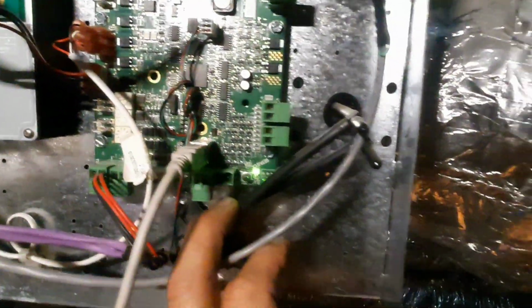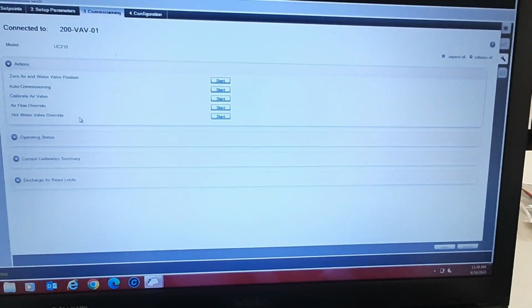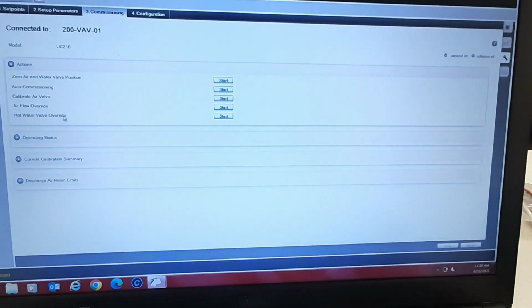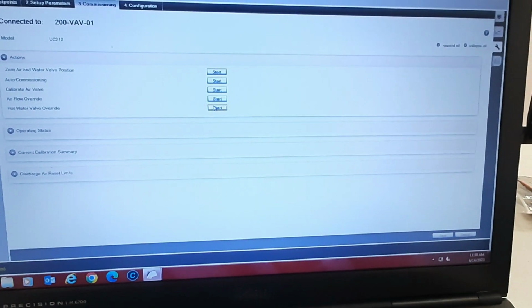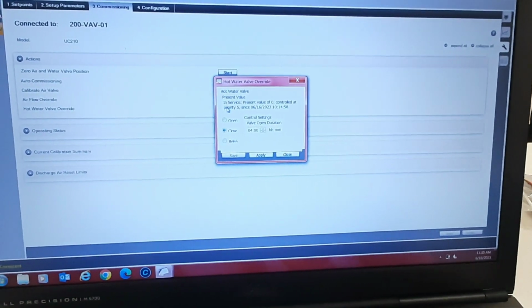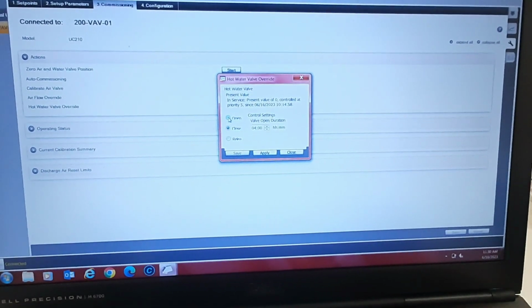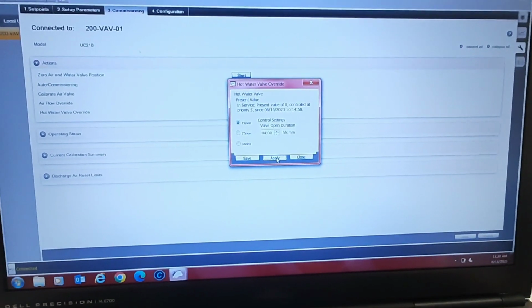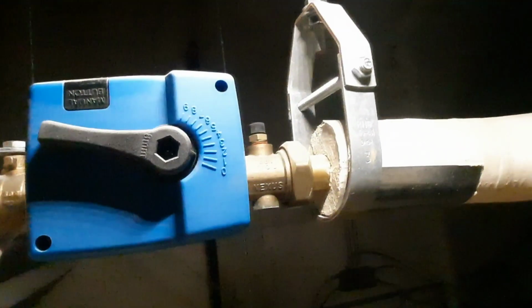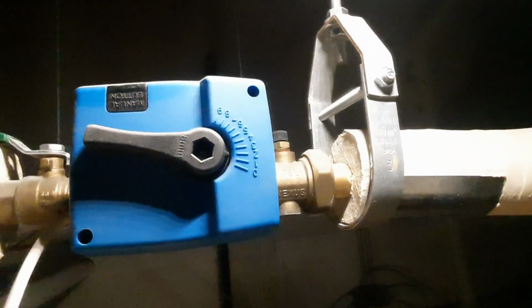Let's see if we can't put it through test mode now. So here we are, we're in commissioning. Let's go to hot water valve override and open, apply. Starting the timeout, let's make sure our hot water valve is gonna operate. Oh yeah, she's opening slowly.